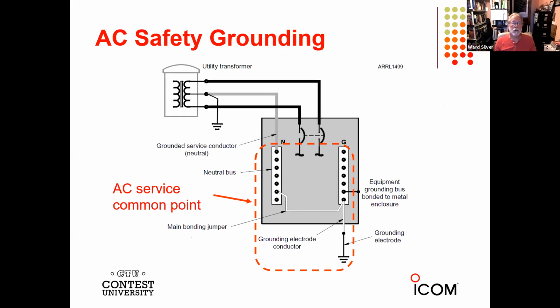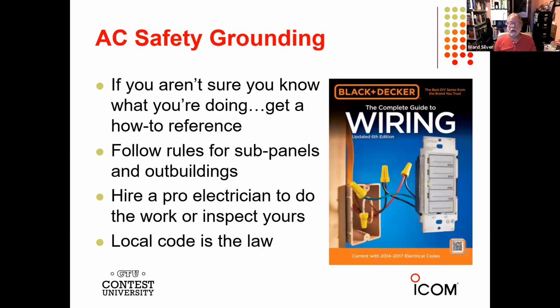Often, almost all the time in major service entries, like in your house, the neutral and the ground buses are tied together with a main bonding jumper, and then that's tied to your grounding electrode outside, which is one or two ground rods. So that is the common service point, and that's where the fault current needs to go in order to trip the breakers.